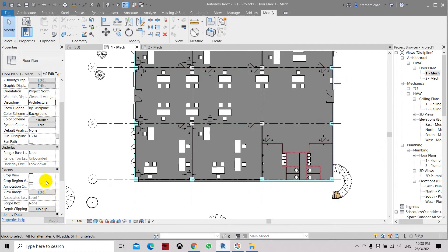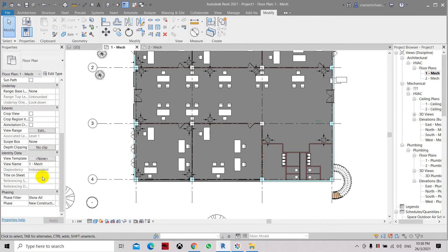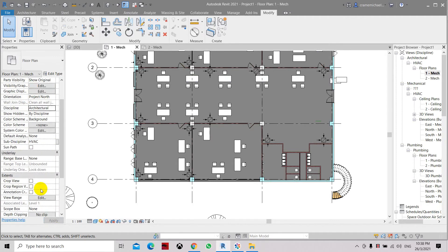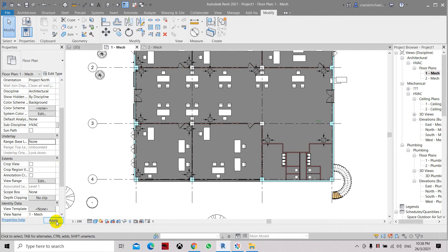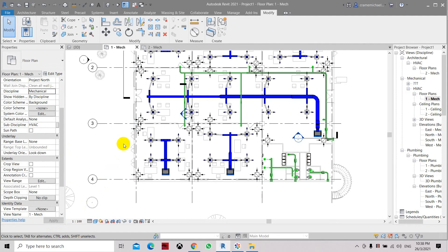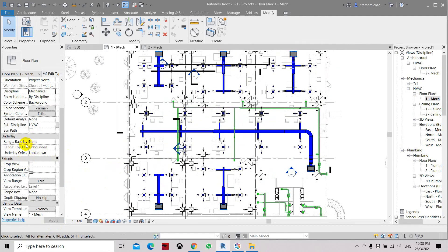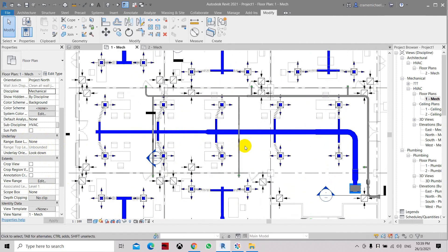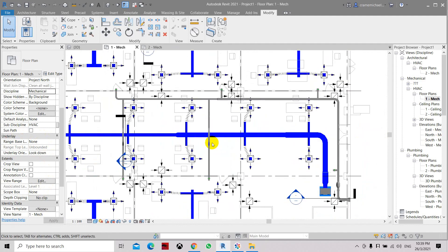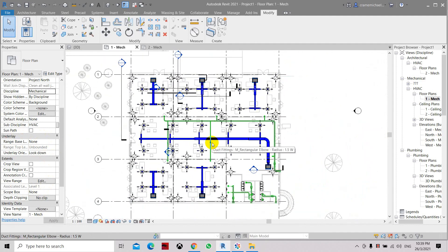We change the associated level which is the range base underlay. Actually we should set it to none because we are not setting any range base level here. The underlay will be none, not level 1. Click apply. Let's go back to the mechanical, click apply. That is the main issue because this underlay means the level below our level 1. So just choose none and you will get back the fitting colors with the same duct color.